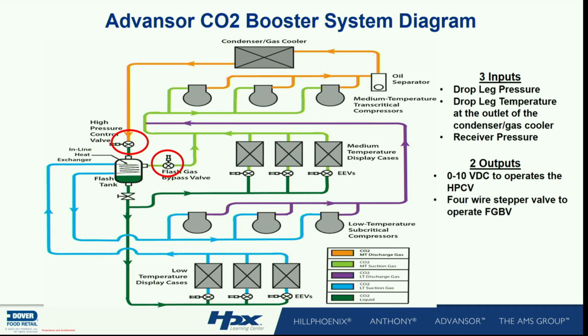How am I going to manage that? So I got a bypass. I got a transducer right there. I simply say, dude, I need to be at 515, 35.5 bar. That's where I want you to be. That's where Hillphoenix, some of the guys, I see some manufacturers are setting at 36 bar. Some are setting it as high as 38 bar. Okay, whatever. Ours is 35.5 bar. Just know what you have to control. But then I simply tell him to manage the vessel, yes?